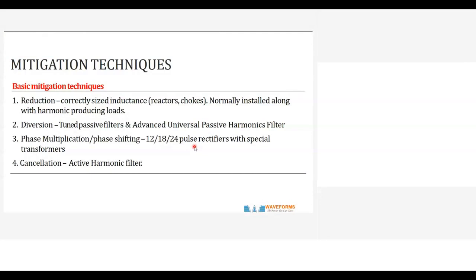When you have multiple drives of the same capacity, you can use this type of multiple output transformer. And then you have cancellation, which is the active harmonic filter. I will tell you about the issues with this active harmonic filter. So the method of the active filter is called cancellation. In phase shifting also, cancellation of harmonics is a technique.